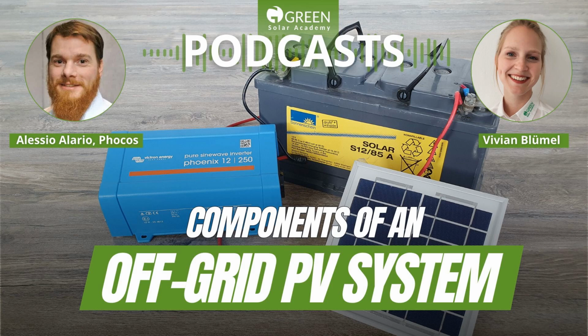So nowadays, only for very small and simple systems would I recommend modified sine wave. Otherwise, if you're unsure, or if you know that you're going to power a whole home, like a whole residential home, then it really doesn't make sense to go with modified sine wave. Certainly not with the larger inverters. Maybe for 100, 200, 300 watts, a modified sine wave will do the trick. If all you're doing is maybe powering a soldering iron or just something that's heating, which again is like a resistive load. Certainly anything above 1 kilowatt, I would go with a pure sine wave inverter.